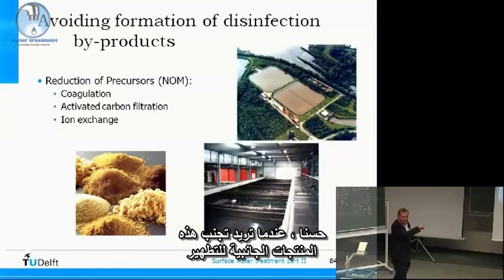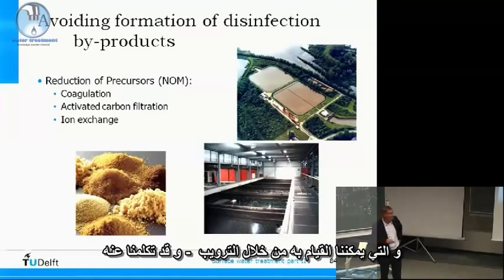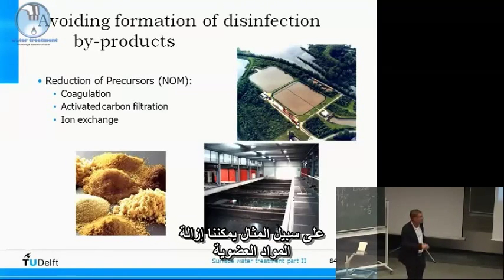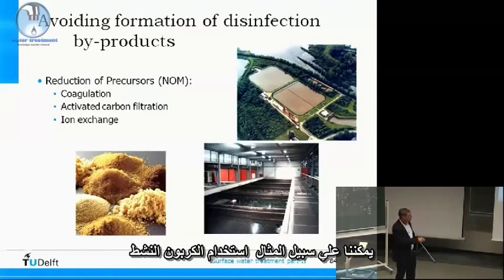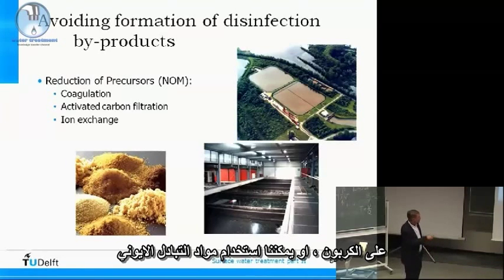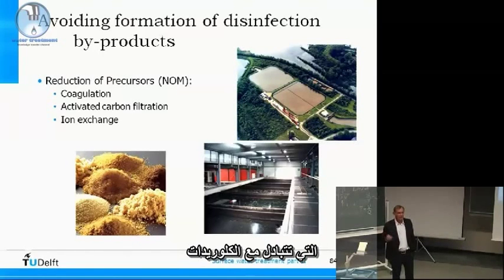To avoid disinfection byproducts, you can remove the organic material before chlorination. This can be done by coagulation at low pH with high concentrations of iron chloride. You can also use activated carbon to remove natural organic matter, or use ion exchange resins to remove humic acids via exchange with chlorides.